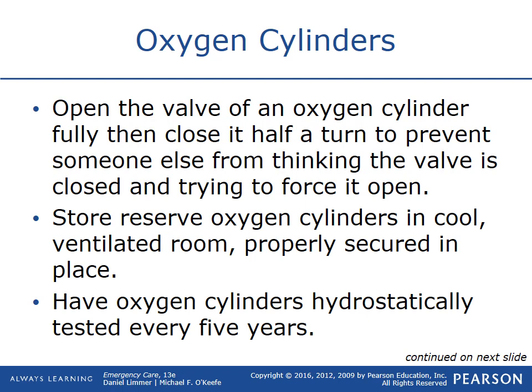When you have an oxygen cylinder, you want to open the valve of the oxygen cylinder fully and then close it half a turn to prevent someone else from thinking the valve is closed and trying to force it open. Store the reserve oxygen cylinders in a cool, ventilated room, properly secured in place, and have oxygen cylinders hydrostatically tested every 5 years.